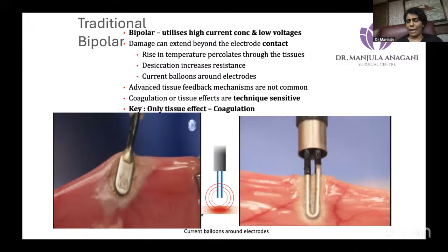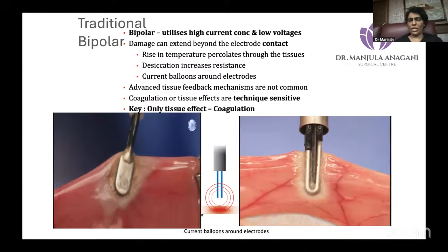Now have a look at this. If you are using a pulse technique, there is no lateral thermal damage. So this is what I say: if you are using your traditional bipolar in a pulse technique, the way advanced bipolar works, then your lateral thermal damage is less because current concentrates at lower voltages. The only effect that bipolar can do is coagulation. Bipolar cannot cut. So technique sensitivity is what we need to understand.